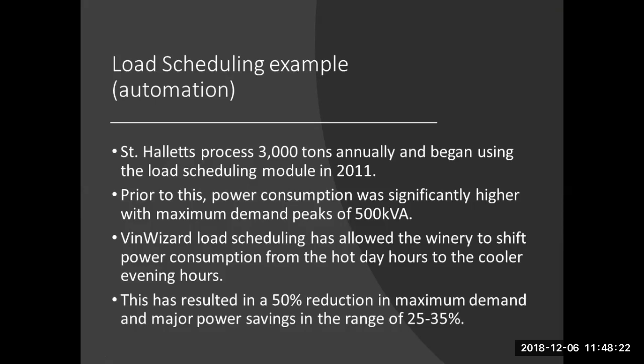Before they did this, they had peak demands in the afternoon of 500 kVA. So that's incurring really massive electricity demand costs. But once they implemented this night cooling, they were able to reduce their peak demand by 50%. So they reduced their peak demand by 250 kVA, which is around $25,000 to $30,000 in savings per annum. So massive savings to be made, and that's simply by shifting refrigeration use.